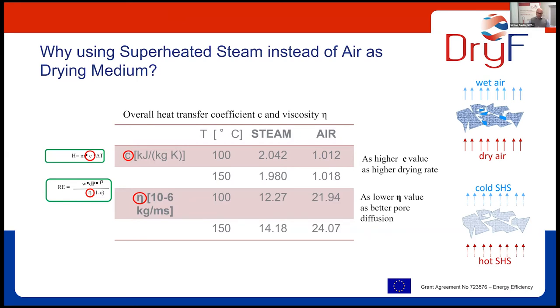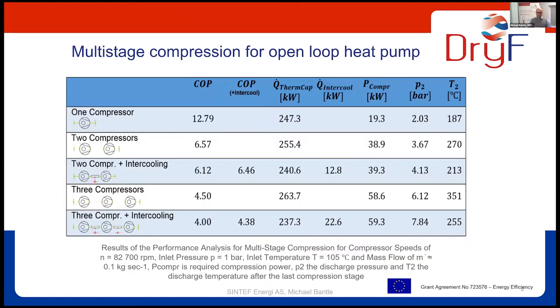There might be other advantages and also disadvantages for using superheated steam as a drying medium, but if you were to choose a drying medium today and we just compare these properties, we would most likely end up using superheated steam and not air. But of course, I know that most dryers are based on air, and that has traditional reasons, and it's also one of the things we have to consider here, where we then need the heat exchange between the air if we want to make our open loop close to. But anyway, just as a general background, that is also why superheated steam is used here. And then some of the technical details.